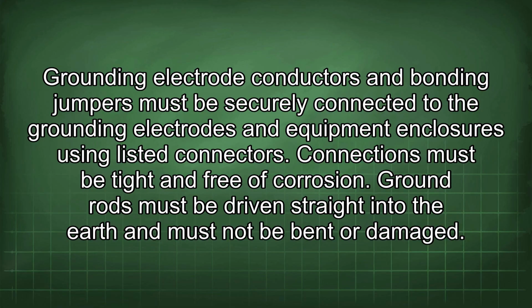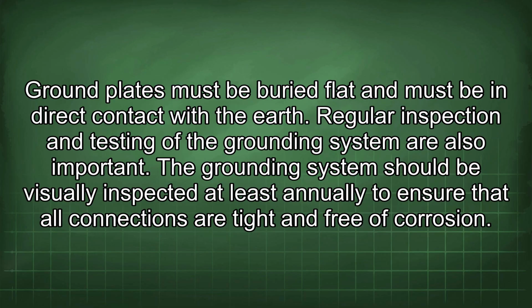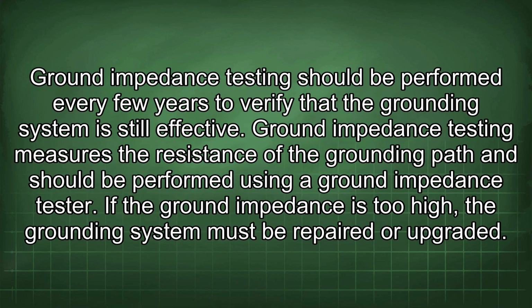Ground rods must be driven straight into the earth and must not be bent or damaged. Ground plates must be buried flat and must be in direct contact with the earth. Regular inspection and testing of the grounding system are also important. The grounding system should be visually inspected at least annually to ensure that all connections are tight and free of corrosion. Ground impedance testing should be performed every few years to verify that the grounding system is still effective.